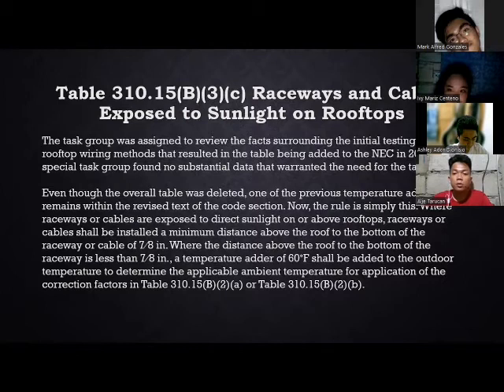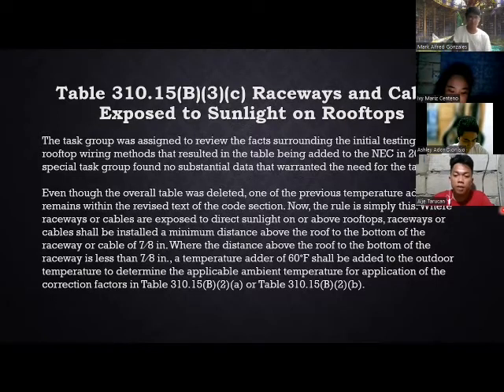section. Now the rule is simply this: where raceway or cables are exposed to direct sunlight on or above rooftops, raceway or cable shall be installed a minimum distance above the roof to the bottom of the raceway or cable of 7/8 inches. Where the distance above the roof to the bottom of the raceway is less than 7/8 inches, a temperature adder of 60°F shall be added to the outdoor temperature to determine the applicable ambient temperature for application of the correction factor to Table 310.15(B)(2)(a) or Table 310.15(B)(2)(b).